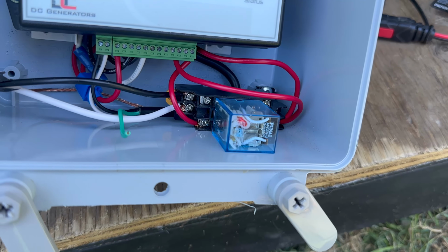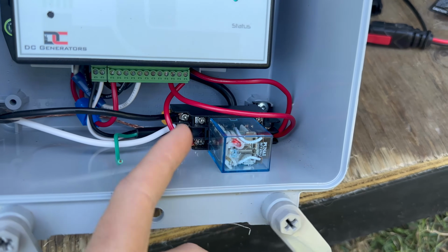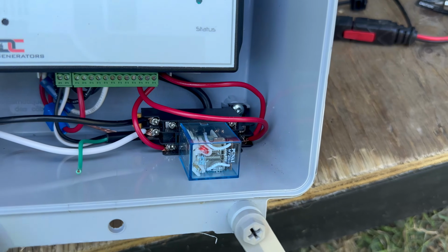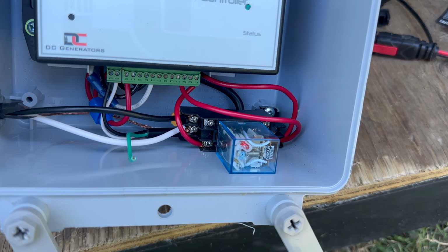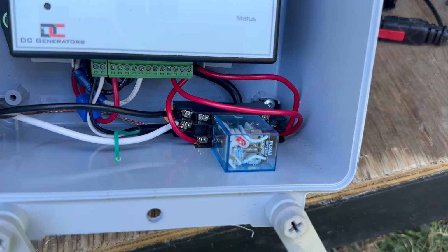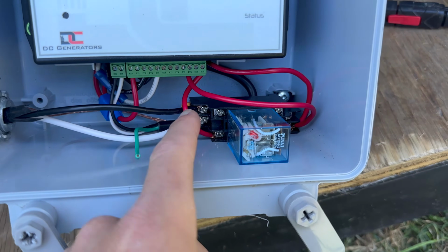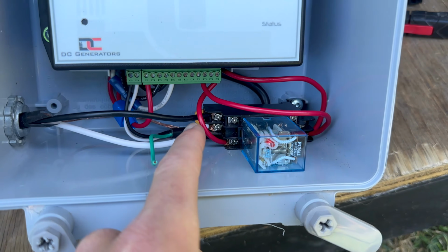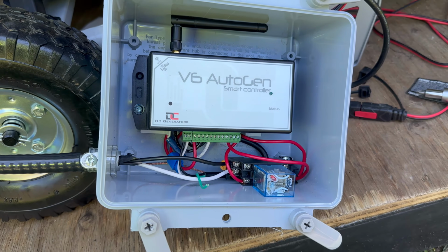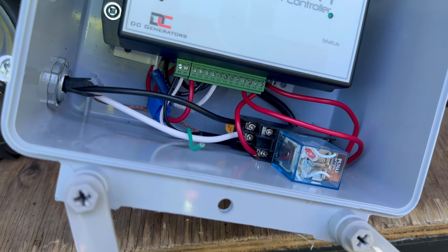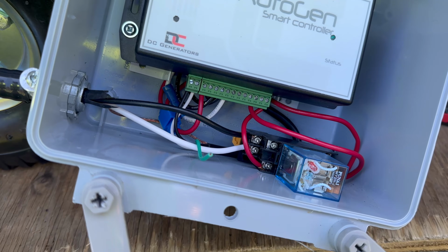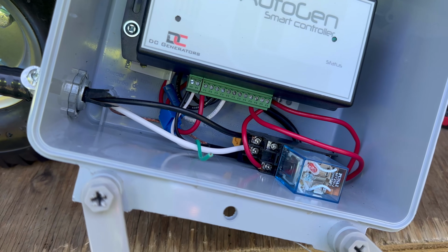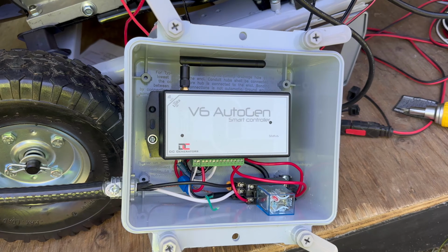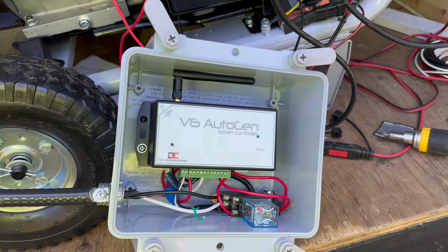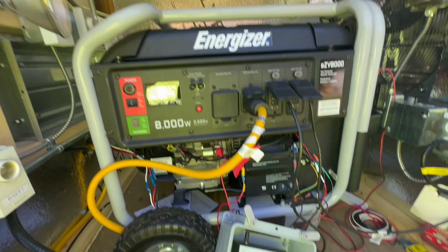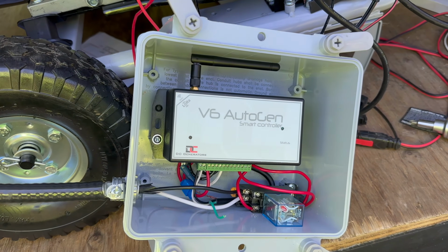When it has 120 volts, this relay will open up the contacts, and this wire and these wires will not be making contact with each other. However, when the 120 volts goes away, when it drops out in a power outage, this relay will deactivate and it will close in, connecting this side to this side, then giving this module 12 volts, telling the module it needs to start. So this 120 volts ties into the BC Hydro line side of the transfer switch, side that is only on BC Hydro. That leads us right to the automatic transfer switch, which none of this has any use if there's not the automatic transfer switch that will transfer the load between sources.